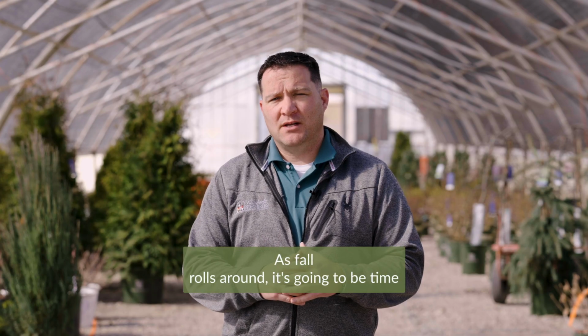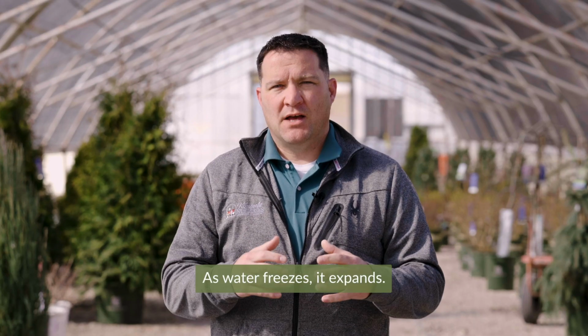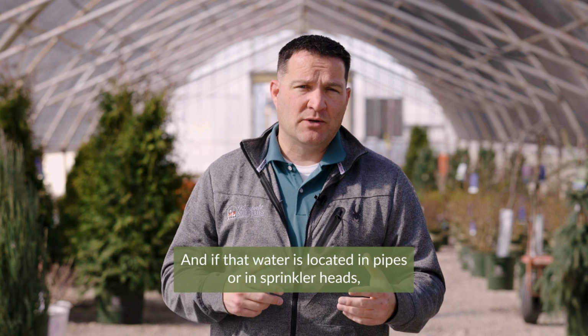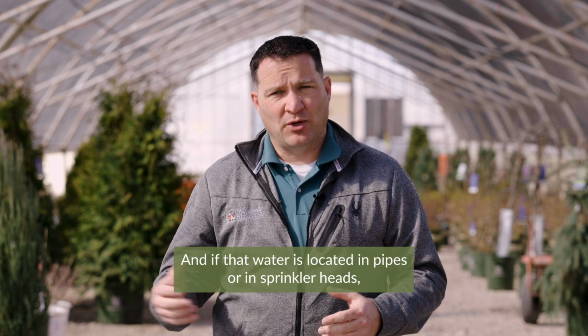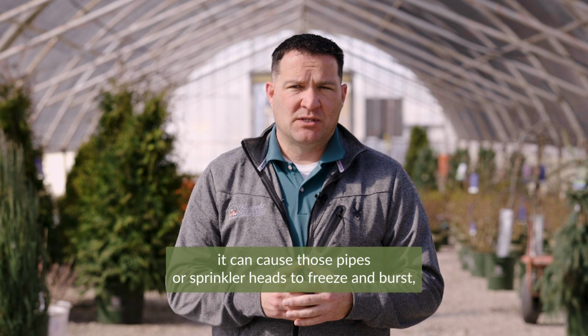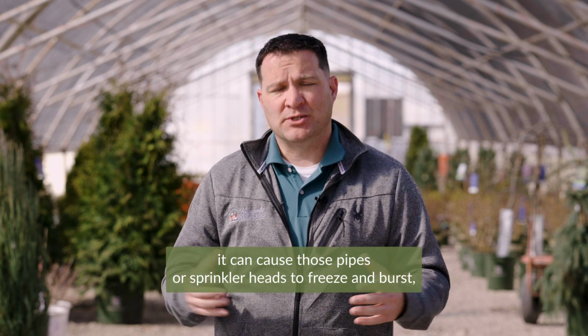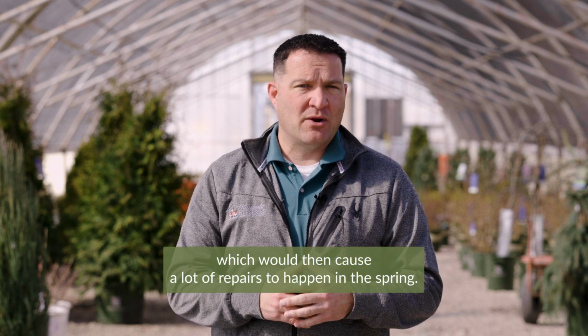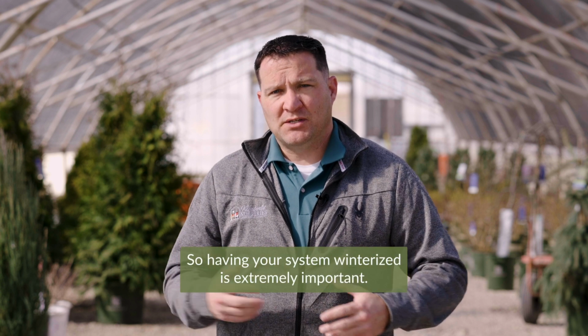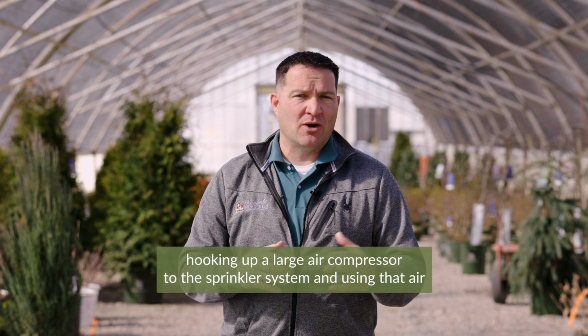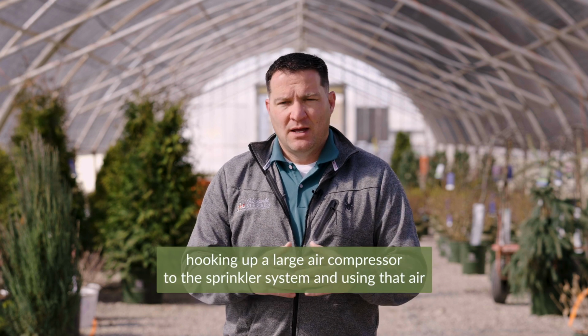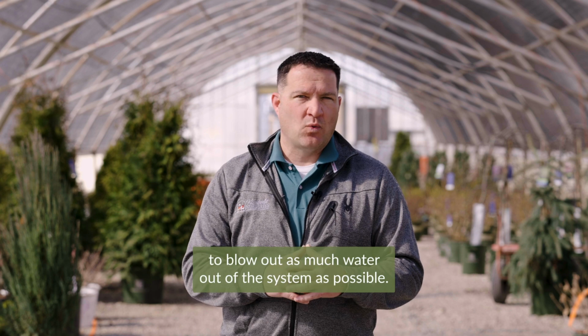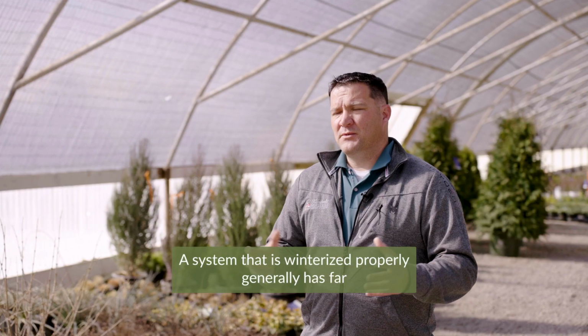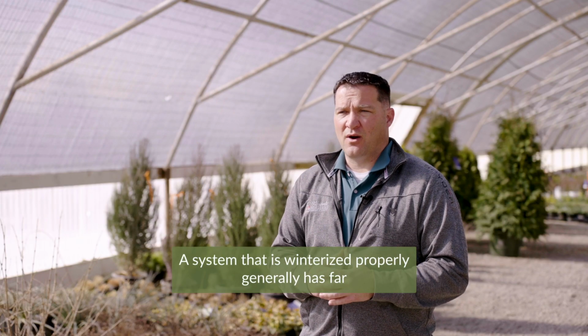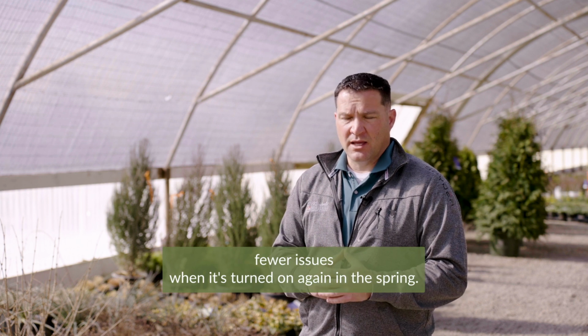As fall rolls around, it's going to be time to get your sprinklers winterized again. As water freezes, it expands, and if that water is located in pipes or in sprinkler heads, it can cause those pipes or sprinkler heads to freeze and burst, which would then cause a lot of repairs to happen in the spring. So having your system winterized is extremely important. The winterization process includes hooking up a large air compressor to the sprinkler system and using that air to blow out as much water out of the system as possible. A system that is winterized properly generally has far fewer issues when it's turned on again in the spring.